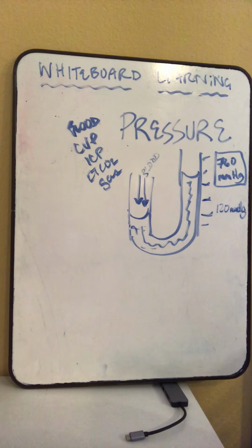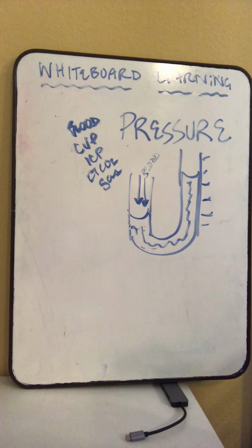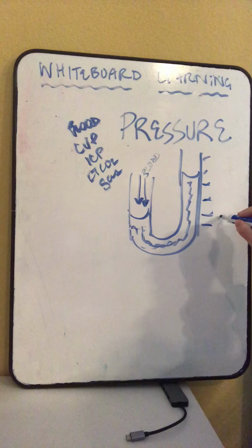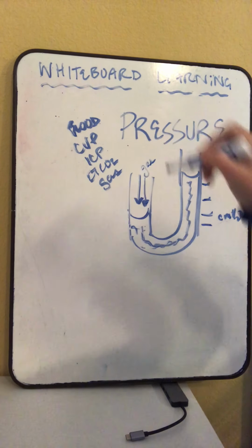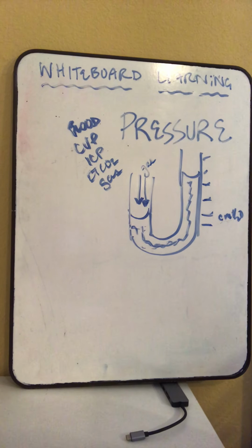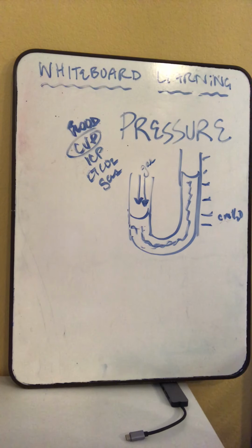Now the other way that we measure sometimes scale-wise is in centimeters of water. So this could be water instead here, and you're going to move things in centimeters of water. And usually that is more reserved for things like gases. So that might be anesthetic gases. Central venous pressure is one that's a liquid that we do in centimeters of water, a lower pressure system.